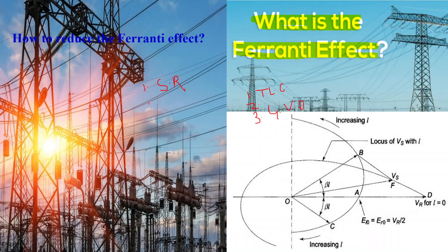Second, series capacitors. Introducing series capacitors at appropriate locations on the transmission line can improve its power factor and reduce the voltage rise. Series capacitors compensate for the line's inductive reactance, thereby improving voltage regulation and reducing the Ferranti effect.